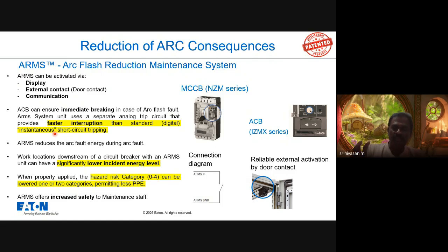For example, assume the instantaneous short circuit protection takes 20 milliseconds to clear the fault, whereas ARMS protection takes less time than the instantaneous protection activation time. By having this ARMS protection, the incident energy level is reduced, and the PPE level can be reduced by one or two categories. Suppose that without ARMS protection the PPE level requirement is PPE3. By having this ARMS protection at the breaker level, it can come down to PPE2 or even PPE1.